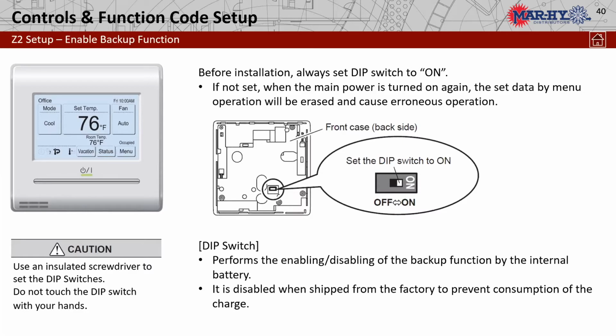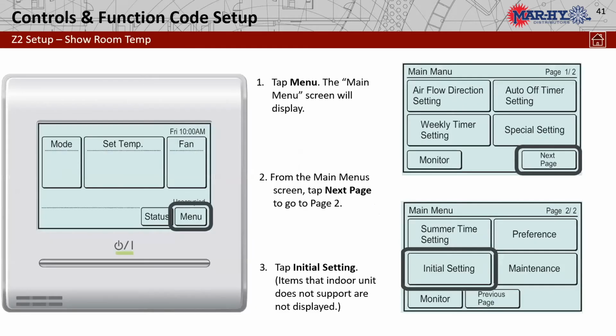So 2 things that must be done on this installation. There's a dip switch in the furnace that needs to be switched on, and there's a dip switch on the thermostat that needs to be turned on as well. Here's your look. It doesn't look real fancy, but it has everything that we need. No colors, but there again, it's very functional.